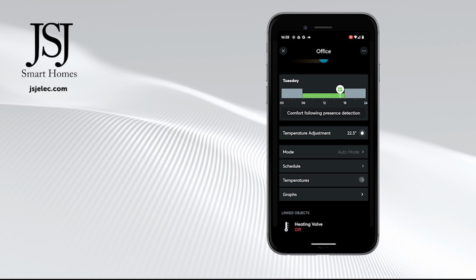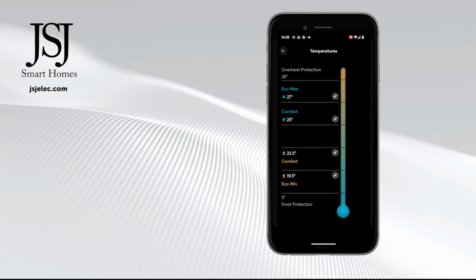We go all the way back to the main screen, and we've got the temperatures here. These are our comfort for cooling, our eco for cooling. So if we are in eco mode, then the range of temperatures allowed within the room is far greater. So it has to get quite a lot hotter before the AC kicks in, or it has to get quite a lot cooler before the heating kicks in.